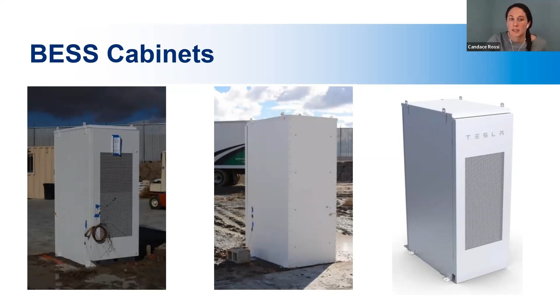This is the battery energy storage cabinet—these are pretty popular. This is an example of an outdoor cabinet system, maybe about the size of two dining room tables, to give you an idea. This is a remote installation, and with remote installations, size and separation isn't required—that's really only an indoor and near exposure requirement.